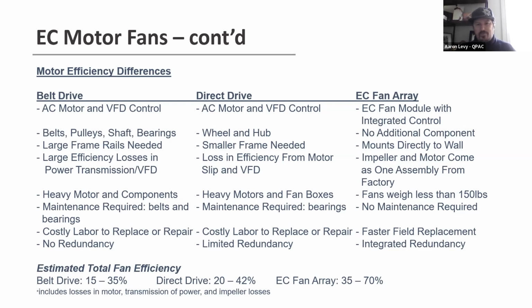It's about 8 or 9 bolts, disconnect a couple of Molex plugs and the pressure tubing. You pull it off the wall, you put another one back up, bolt it up in its place, and then plug those back in. And then the system can be up and running relatively quickly without a lot of downtime for the customer, as well as integrated redundancy. If you lose a belt, you've got nothing. If a motor burns up, you've got nothing on a belt drive system until you can have that replaced.